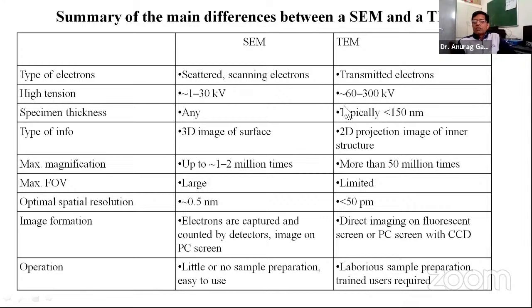And if the voltage is high, naturally the resolution will be better because the wavelength of the electron will be smaller. On specimen thickness, I told you that in SEM the thickness does not matter, because we do not transmit the electrons; they come from the surface. So any thickness can work for SEM, but in TEM the thickness should typically be less than 150 nanometers, so that the highly energetic electron beam can be transmitted across the sample. On magnification, SEM can magnify the image 1 to 2 million times, but TEM more than 50 million times. So naturally the resolution of TEM is better than SEM.